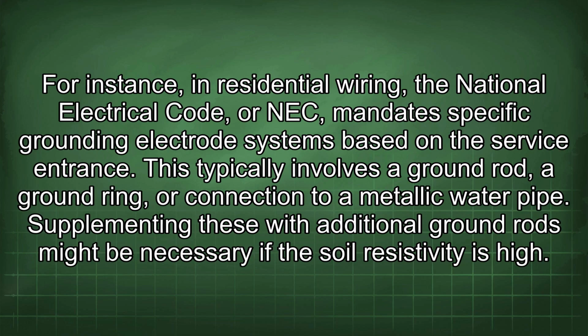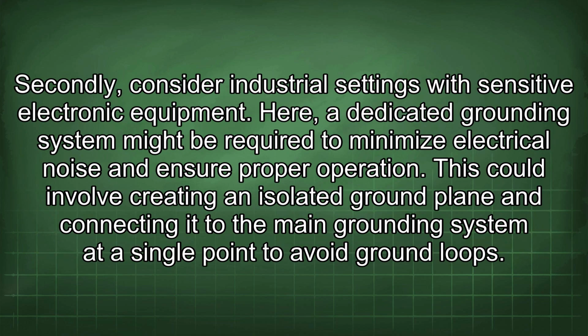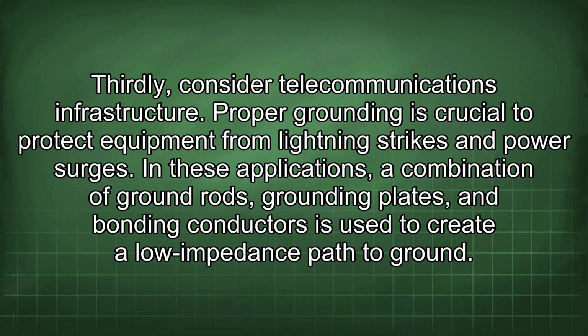For instance, in residential wiring, the National Electrical Code, or NEC, mandates specific grounding electrode systems based on the service entrance. This typically involves a ground rod, a ground ring, or connection to a metallic water pipe. Supplementing these with additional ground rods might be necessary if the soil resistivity is high. Secondly, consider industrial settings with sensitive electronic equipment. Here, a dedicated grounding system might be required to minimize electrical noise and ensure proper operation. This could involve creating an isolated ground plane and connecting it to the main grounding system at a single point to avoid ground loops.